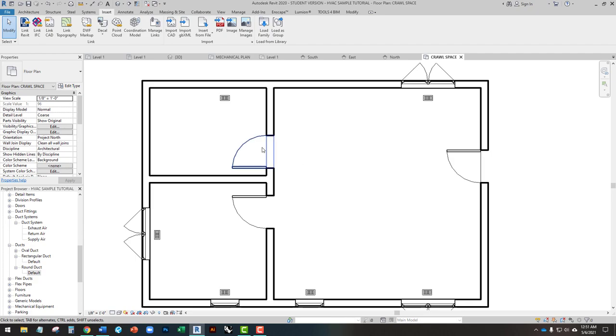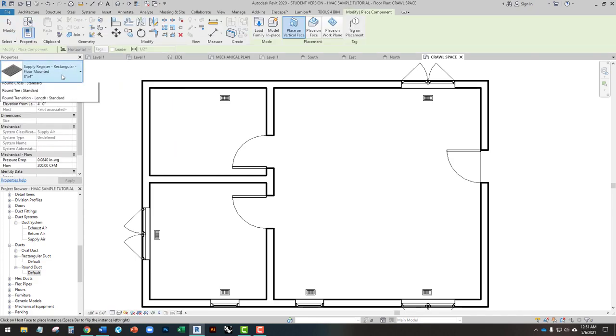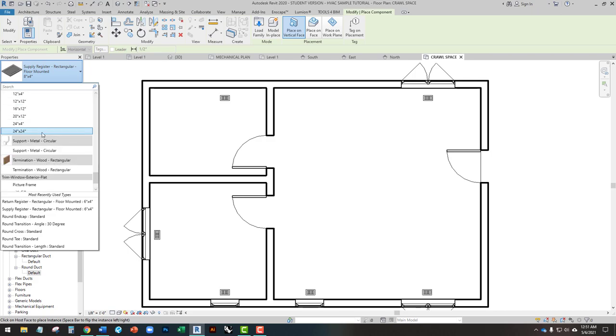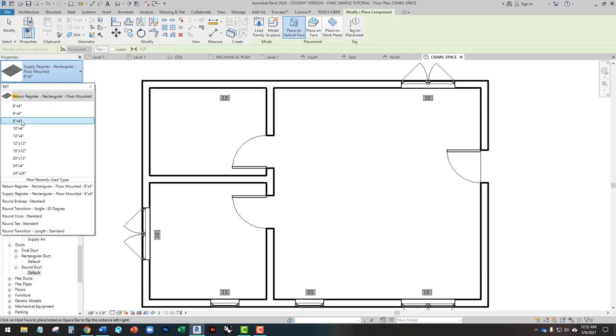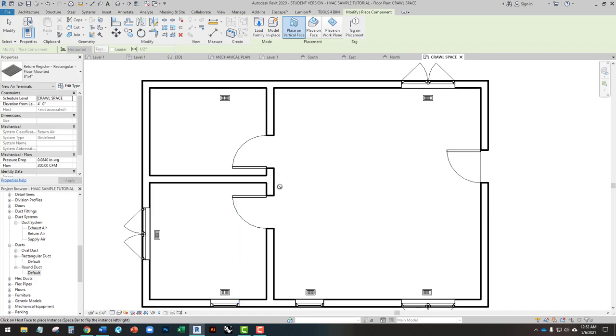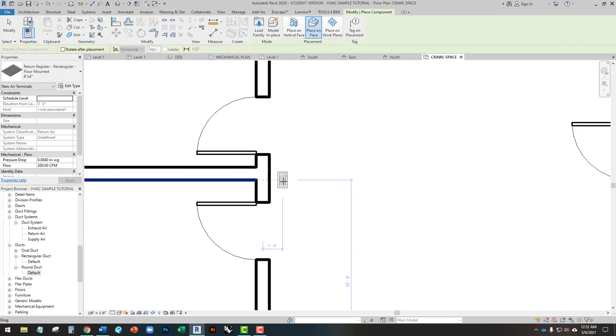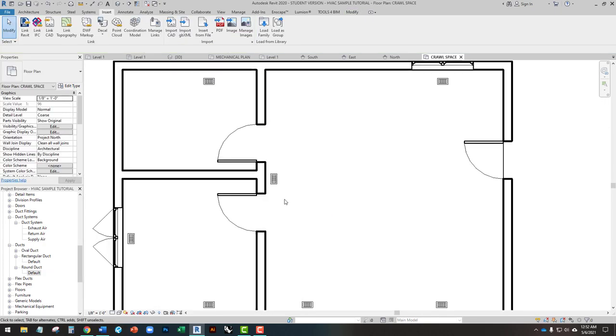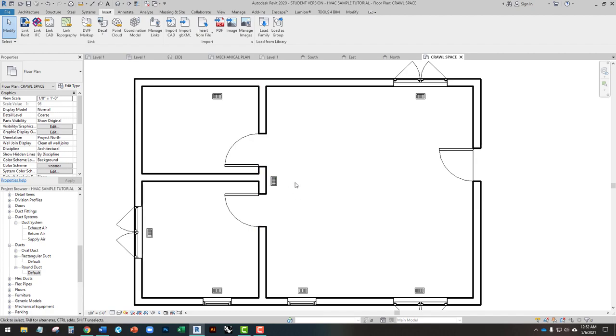I'm going to supply to the perimeter and have one return in the center — centrally located, far enough from all the supply so we don't have a closed loop. I'm going to go to CM for Component, and instead of supply, I'll add a Return Register — an 8x4. I have to place on face, hit Space Bar, and place it right here. This could also be wall-mounted, or all of these could be ceiling registers. The air handling unit could be on the floor, in a mechanical closet, or in the attic — in this case, we're putting it in the crawl space.